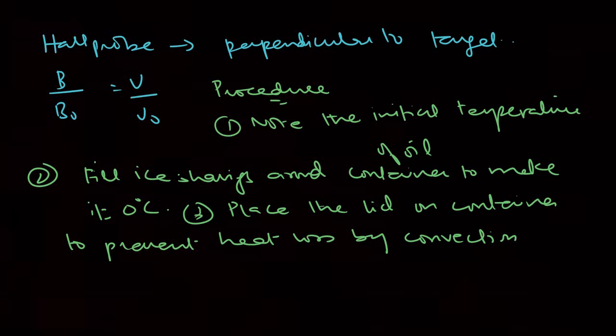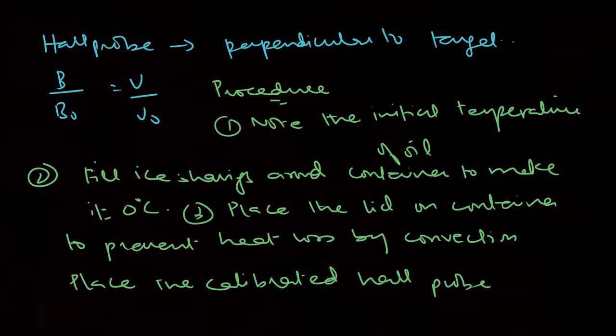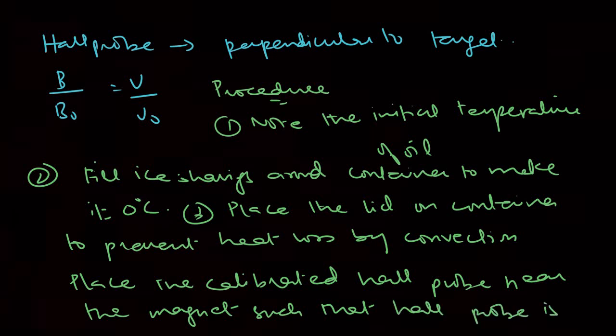When the thermocouple shows 0 degrees, place a calibrated Hall probe near the magnet. So place the calibrated, again these wordings, Hall probe near the magnet such that the Hall probe is perpendicular to the magnet.